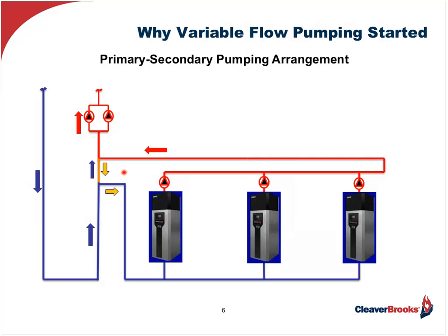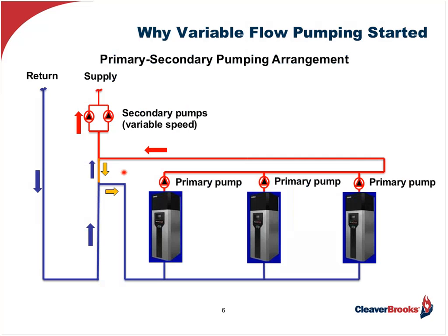Now you're going to hear me talking about primary, secondary, and variable flow, primary variable flow pumping. So let's talk about the differences real quick in the system components. You're going to have a supply and return pipe out to the system. You're going to have your secondary or system pumps. Those are going to be your variable speed pumps. Then you will have your primary pumps, or a pump for each boiler. Now, we're not going to show them on these schematics, but each one of those pumps will have a starter, a check valve so you don't have flow back through the boilers, and typically a strainer as well.